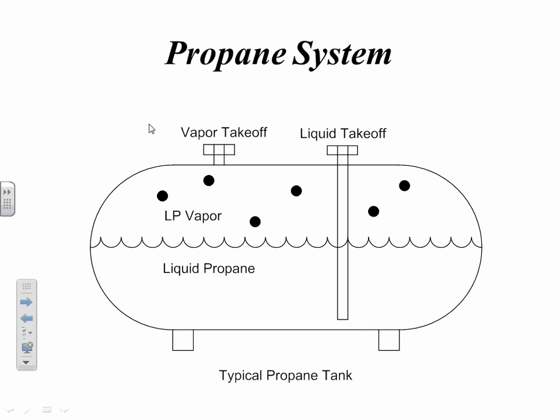And what that does for us is two things. If we had a vapor tank, there's two ways to fix that problem of not vaporizing enough fuel. We could oversize this tank to the point where it filled up most of the room, but we'd have enough vapor to run the generator set. That's not really a cost-effective solution. But if we take it off as a liquid and vaporize it, we can optimize the size of that fuel tank. We can get it as low as we want to. In a legally required system where we have an automatic backup, technically by the rule, we only have to have a 2-hour on-premise supply. So we can get this tank size down quite a bit.